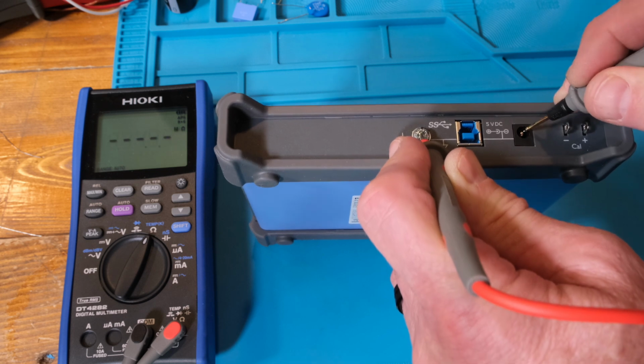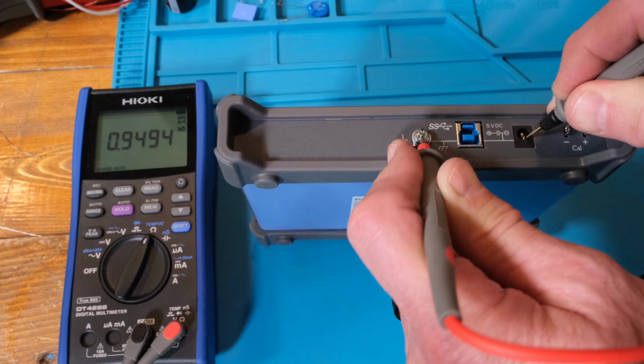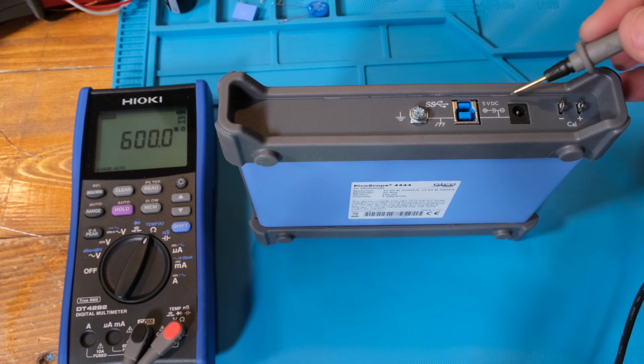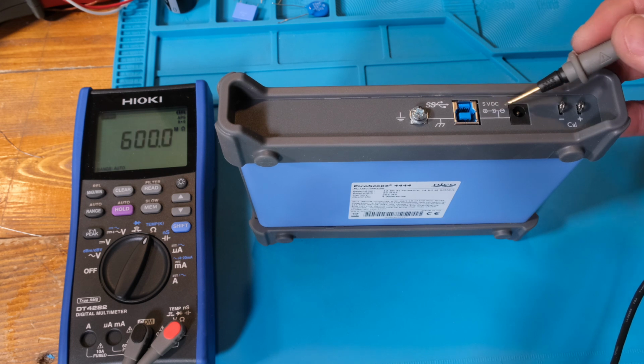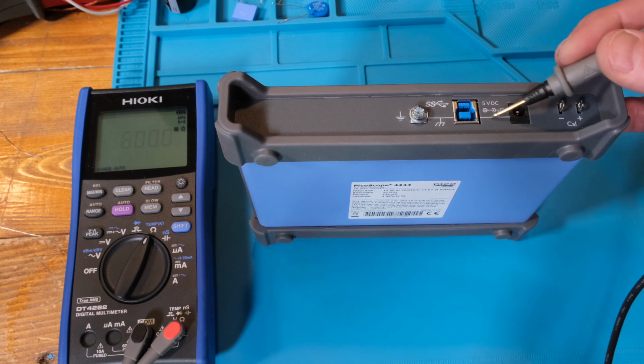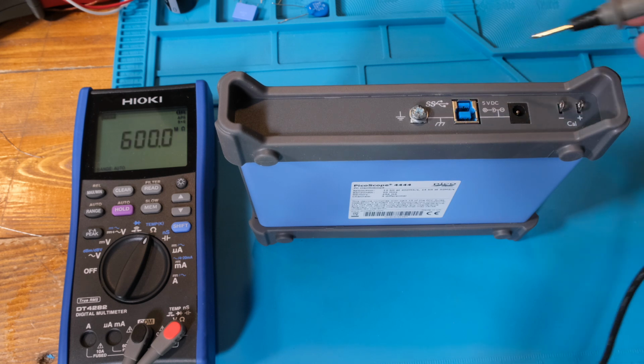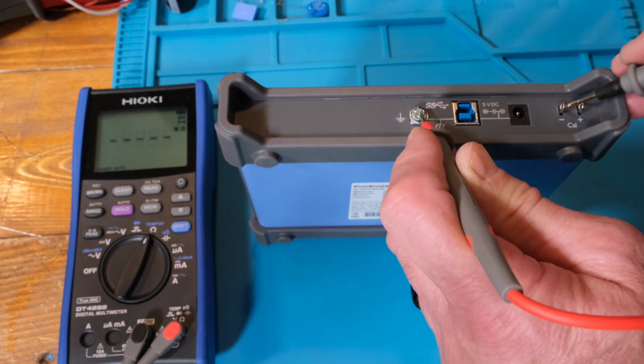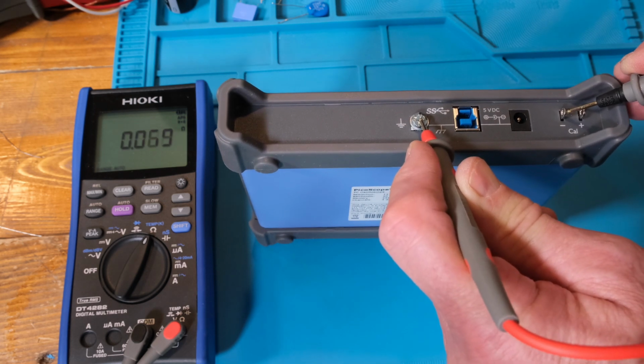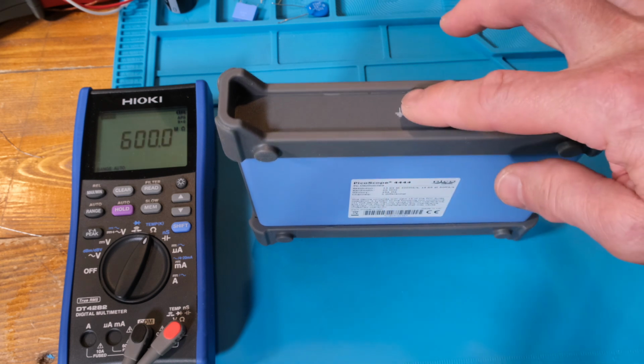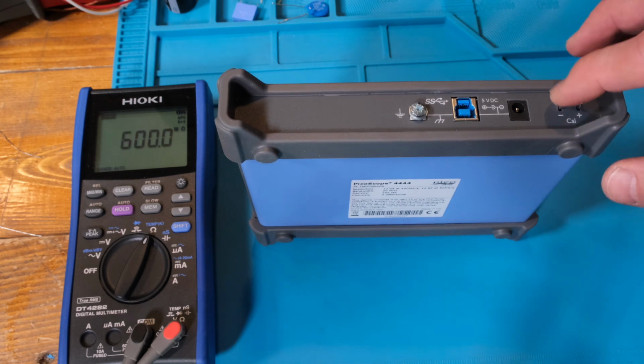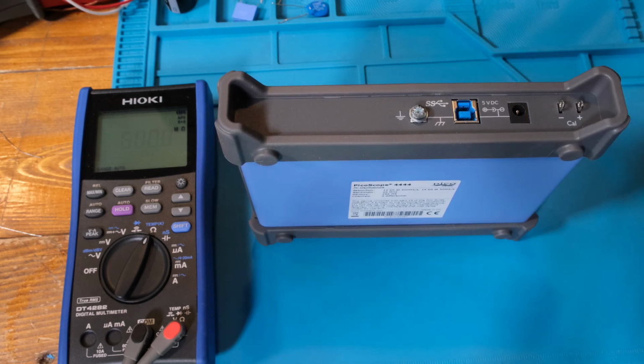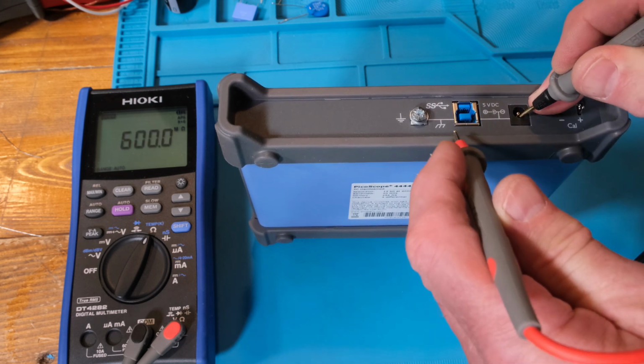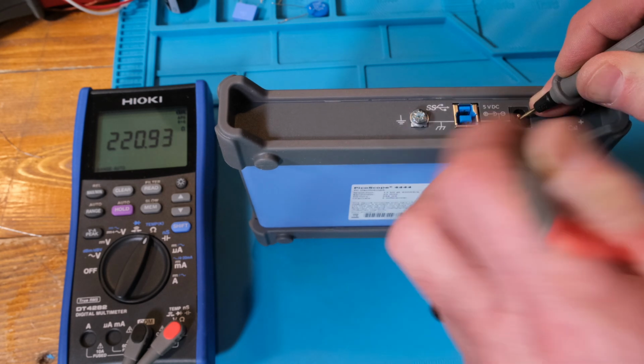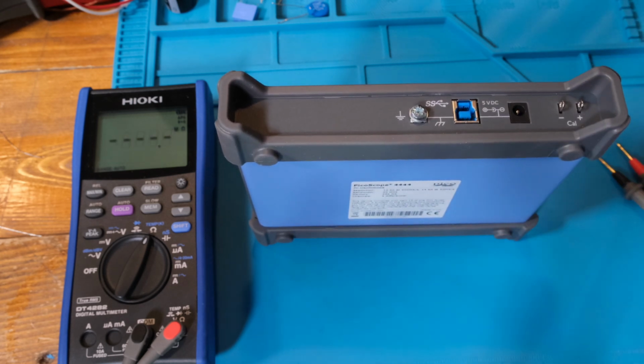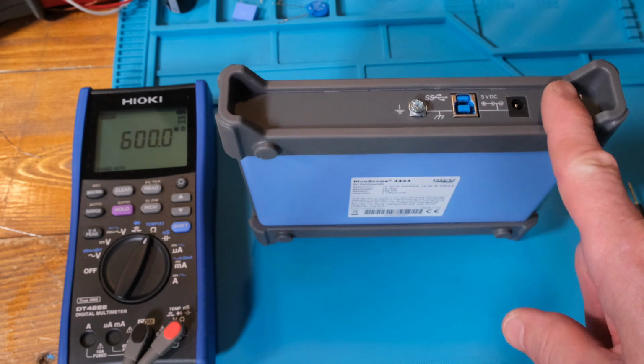So if I touch either one of the terminals, or both even, it doesn't seem like it's tied to this guy. So now there is a shield. This shows the plus and minus and kind of a shield around it. So maybe there's a shield around the power that's tied to chassis, but the power itself is not. And then the minus pin over here looks like it's tied. So, okay, that's interesting. So if you tie this to chassis, you can tie your minus and your shields to chassis, but the power still looks like it's isolated from chassis. Or once you tie that to earth ground, it still looks like it's isolated, although the minus pin is not. That's interesting.